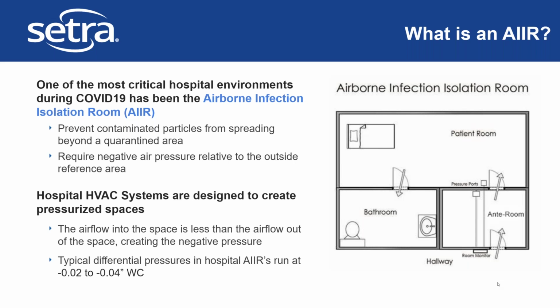The hospitals have their HVAC systems designed to create these pressurized spaces. And so you can see the arrows in the room pointing to the direction airflow would go because of the negative pressure. It's negative relative to the hallway, and typical airborne infection isolation rooms are run at a differential pressure of negative 0.02 to negative 0.04 inches of water column relative to that outside area. And again, that negative pressure is key to this isolation and the protection of other people in the area from the contaminated particles inside. Let's jump to the next slide.